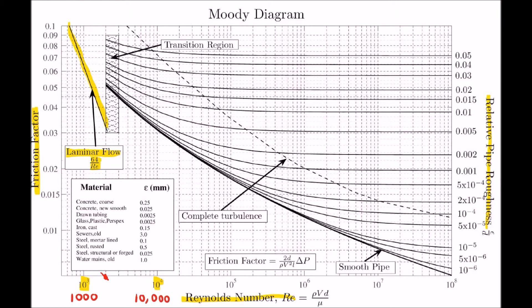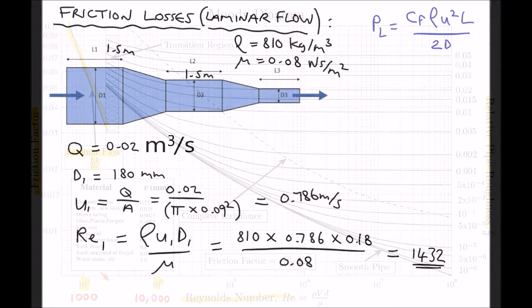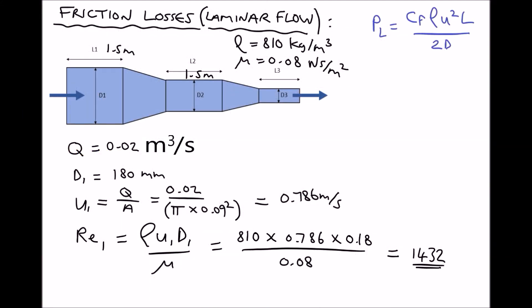Let's return to our calculations. We can determine our friction factor using the formula, and then calculate the pressure loss using the Darcy equation. From the Moody diagram, the friction factor Cf is 64 over the Reynolds number. In this case we have a Reynolds number of 1432, so 64 over 1432 equals 0.0447. That's dimensionless, so our value of Cf is 0.0447.